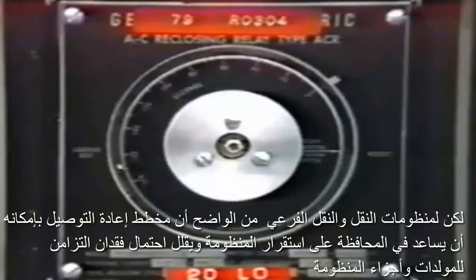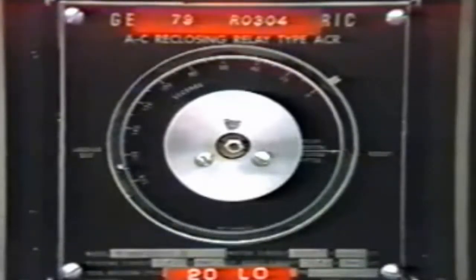The operation of the recloser is mechanical, and usually up to 4 attempts are provided with time delay settings between each attempt. Again, all of the settings need to be coordinated with other protection devices on the feeder, particularly the feeder breaker. Actually, the operation of reclosers on the distribution system does not really affect the stability of the power system very much. They are installed with the objective of reducing outage time to the customers. However, on transmission and sub-transmission systems, it's clear that reclosing schemes can help retain stability of the system and reduce the likelihood of generators or parts of the system falling out of step. But unfortunately, instability can and occasionally does occur.